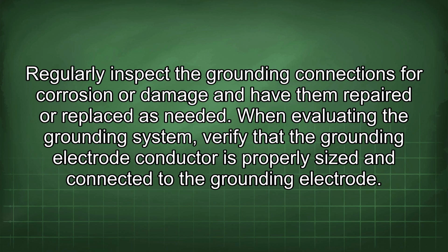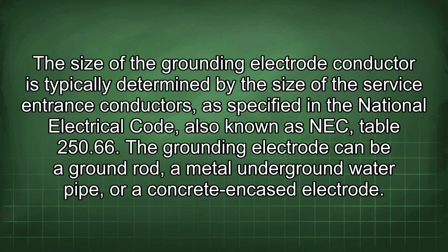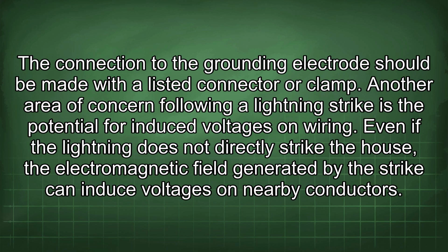When evaluating the grounding system, verify that the grounding electrode conductor is properly sized and connected to the grounding electrode. The size of the grounding electrode conductor is typically determined by the size of the service entrance conductors, as specified in the National Electrical Code, also known as NEC Table 250.66. The grounding electrode can be a ground rod, a metal underground water pipe, or a concrete encased electrode. The connection to the grounding electrode should be made with a listed connector or clamp.